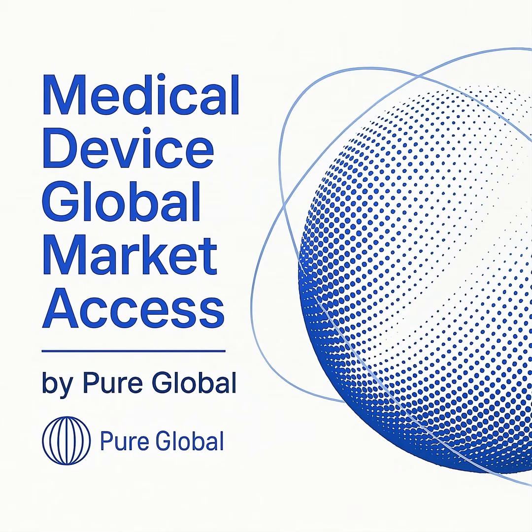The new guidance, effective June 4, 2026, changes this landscape. Recognizing that many of these unclassified devices have a long history of safe use and pose a low risk to patients, the FDA has determined that 510(k) pre-market notification is not necessary to provide a reasonable assurance of their safety and effectiveness. The guidance provides a specific list of device types that are now exempt. This action is part of the FDA's broader effort under the 21st Century Cures Act to reduce unnecessary regulatory burdens and focus its resources on higher-risk devices, thereby fostering innovation and patient access. This directly impacts manufacturers currently marketing or developing products that fall under the umbrella of these newly exempted unclassified devices.